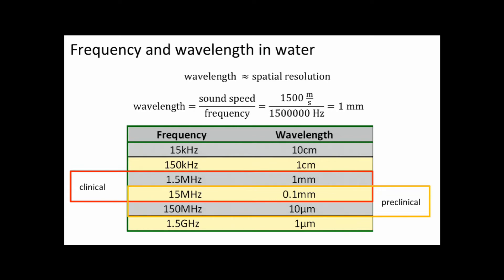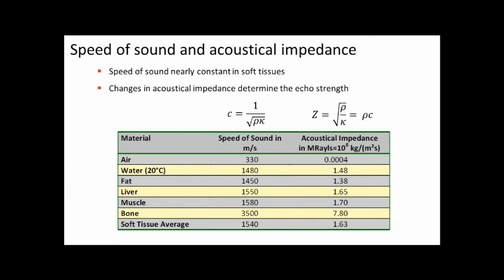Preclinical small animal scanners typically start at about 15 megahertz and go up to about 50 to 70 megahertz, so the resolution can be much higher and you can image mice and rats in very good resolution. We assume in ultrasound imaging that the speed of sound in tissues is constant — one of the assumptions that is not really true. Looking at fat, liver, muscle, and soft tissue, the average is about 1540 meters per second, all very similar — about 10% difference between them. Air and bone are completely different.